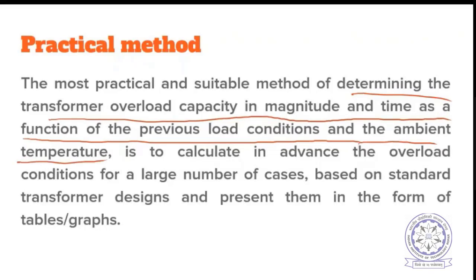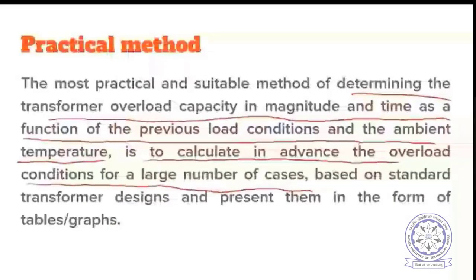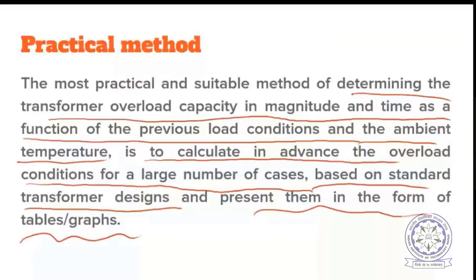So the current temperature depends on the previous load conditions as well as the ambient temperature. Based on the design of a transformer, it is possible to estimate the temperature rise for a given history of the load and ambient temperature. This can be calculated in advance for a large number of overload cases, for example different types or levels of load, based on the standard transformer design, and then presented in the form of tables or graphs. This is the most practical method adopted in the transformer industry.